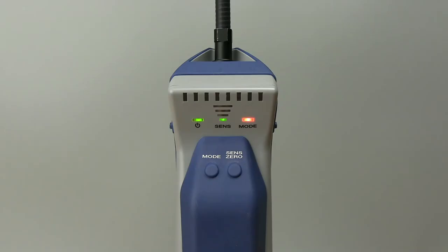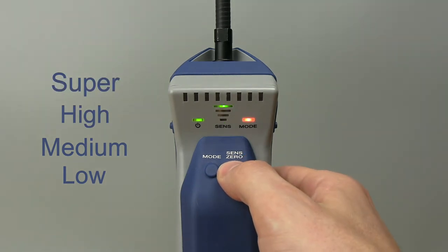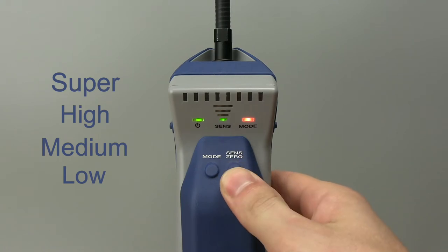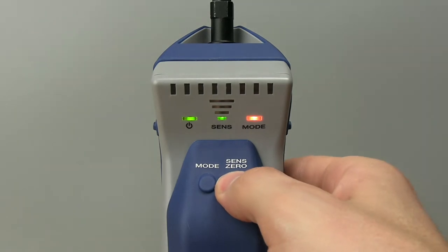Pinpoint mode has four sensitivity settings: Low, Medium, High and Super. While Super is the most sensitive, it may not always be the best for your application. For large leaks, a lower sensitivity setting may work best. Toggle between sensitivities by pressing the Sense Zero button.